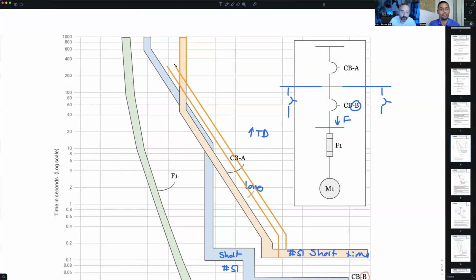Does that get us out of the miscoordinated region? That would be like shifting this whole thing up, and again, this overlap is gone. Here's our new curve—if this was filled in beige, we would no longer have any miscoordination. Does that make sense? Yeah. It's not a possible answer choice here, but it is another viable way to fix the coordination: we could have either increased the tap setting, shifting the whole curve to the right, or increased the time dial, shifting the curve vertically—right and up, away from circuit breaker B.